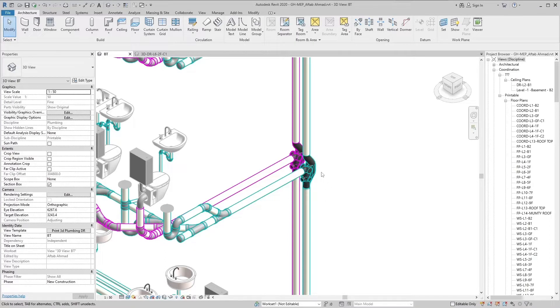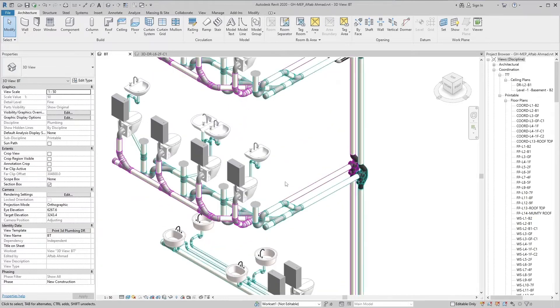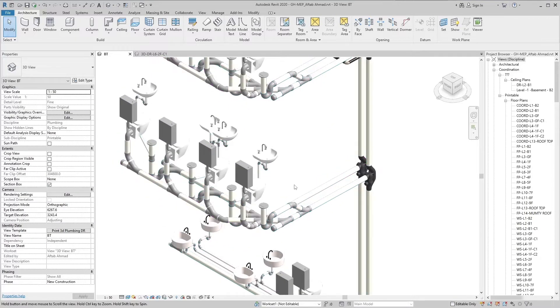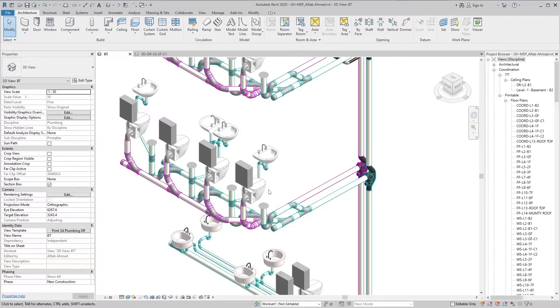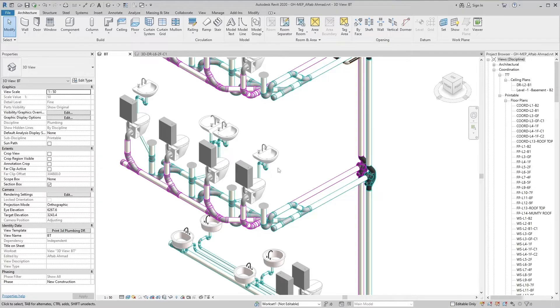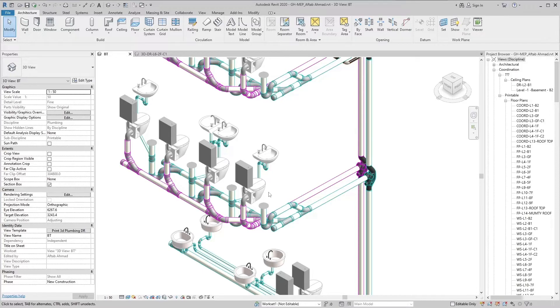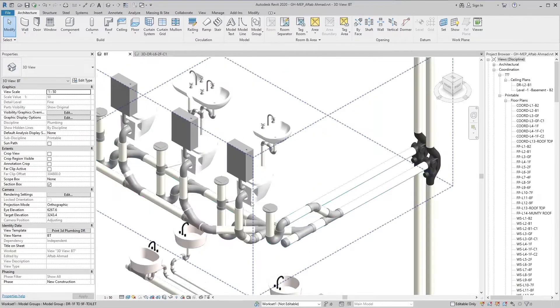In drainage systems we have two types of waste: first is solid waste and second is liquid waste. It is a proven fact that terminal velocity of water is between 3 meters per second and 6 meters per second for water and solids in the range of 15 meters per second.